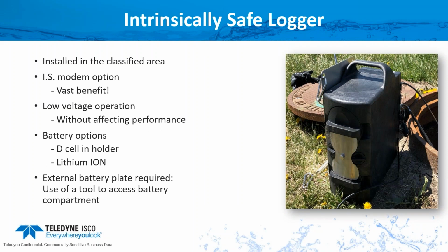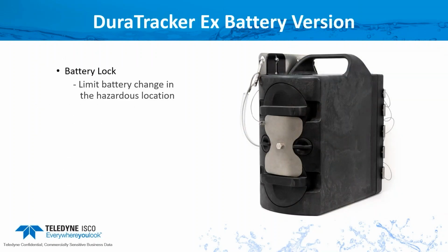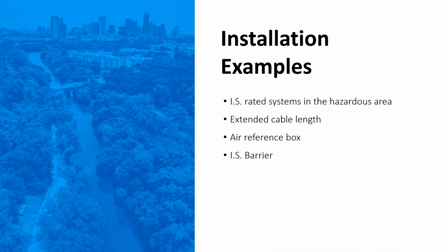And on the outside, you'll notice there's an external plate, and a tool is required to access the battery compartment. The reason is that we have a battery lock on there. It limits battery changes in the hazardous area. So again, we're trying to minimize risk by essentially requiring you to pull the meter out of the classified area, set it above ground, and then you can pull the batteries out. We want to eliminate any possibility of a spark. And as I mentioned, we're using the D-cell battery holders or lithium-ion batteries sold through ISCO.